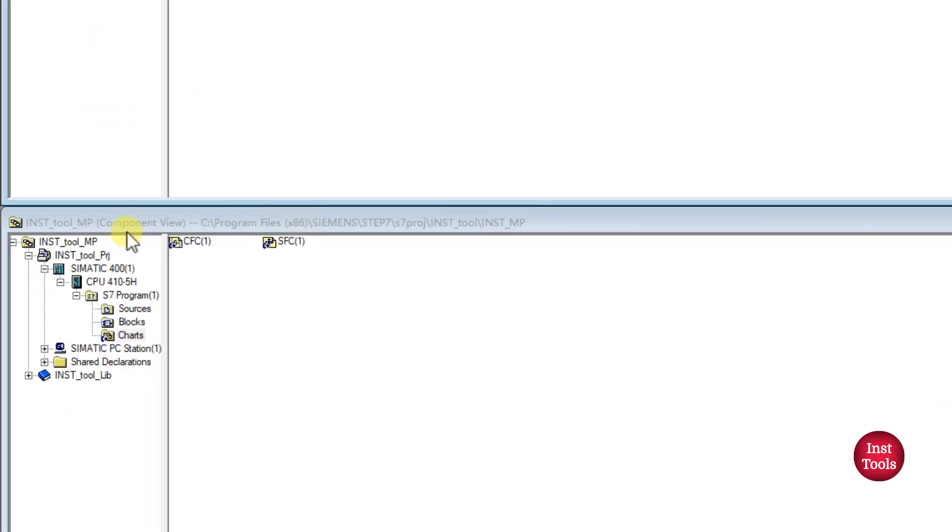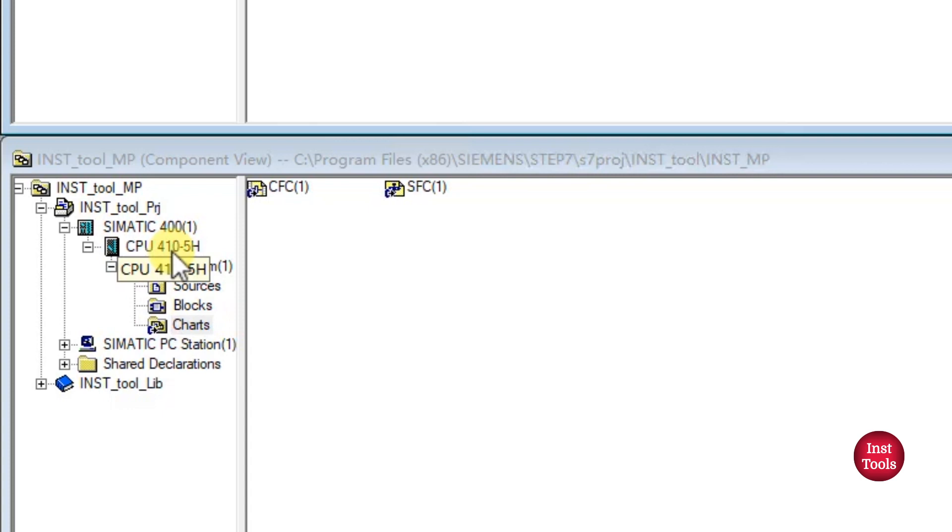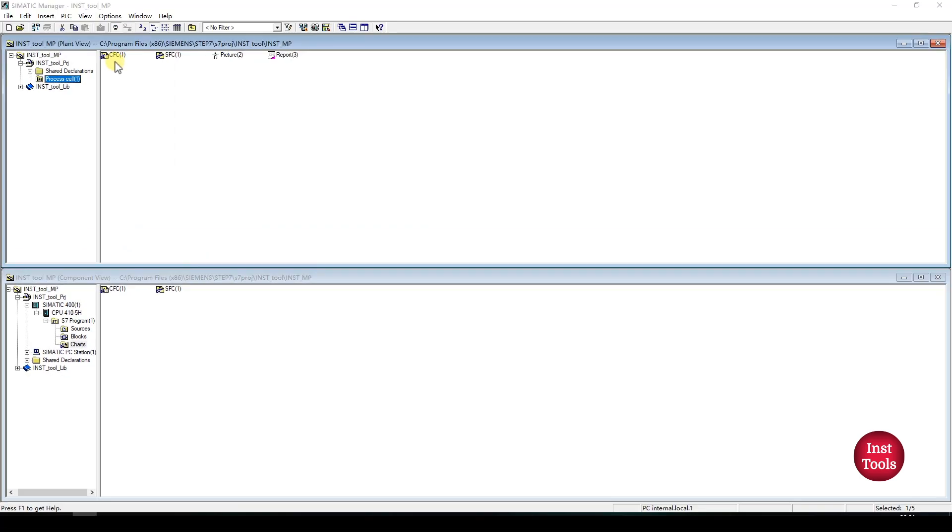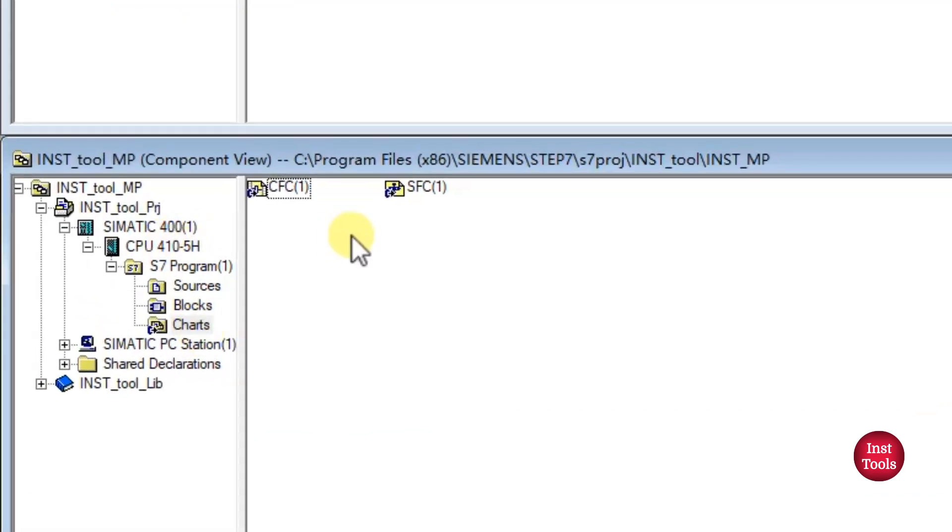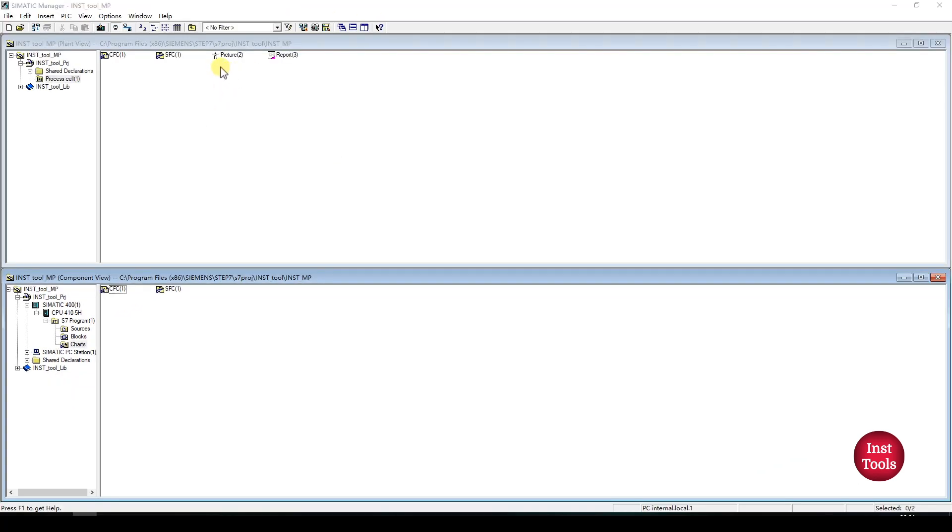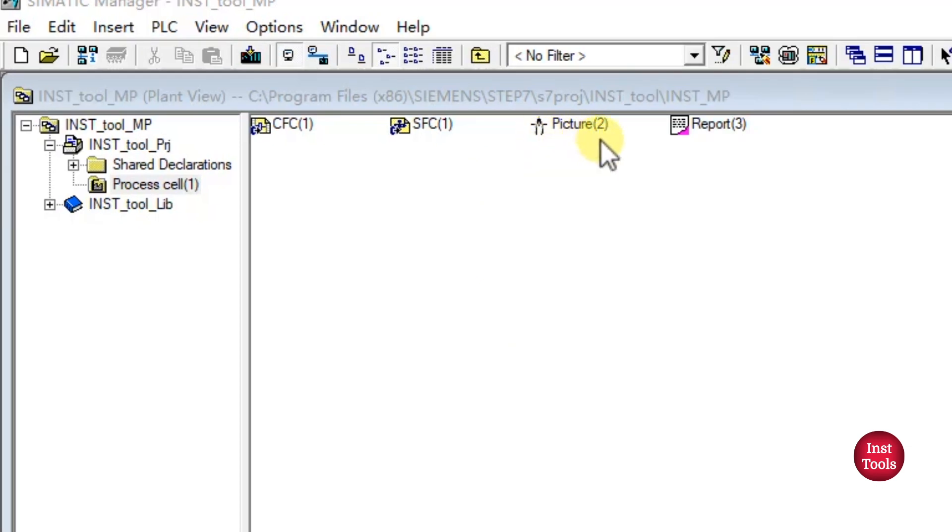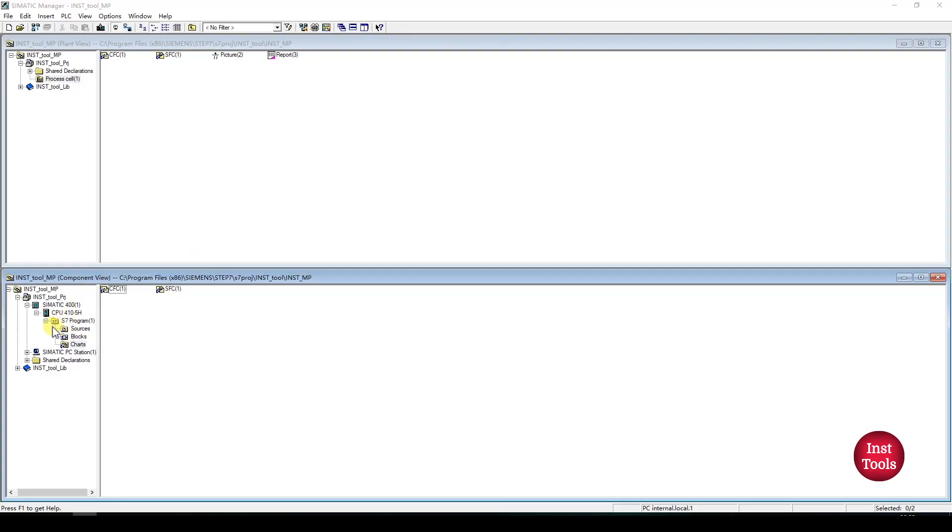And in Component view, we will have the ES and OS structures. Here we have selected 410-5H processor and all the CFC and SFC logical parts which we have derived in plant view will be automatically placed in corresponding charts of ES. Here under the charts folder, we will have those logic parts. Here you can see the picture, which means this is a display point. This display point and report point will be coming under the OS. Here we have configured Simatic PC station with single OS. Under this OS, we will get those two pictures.